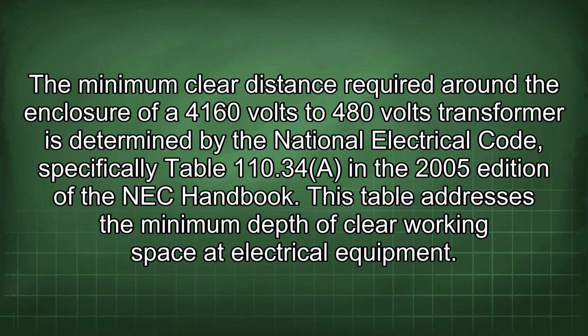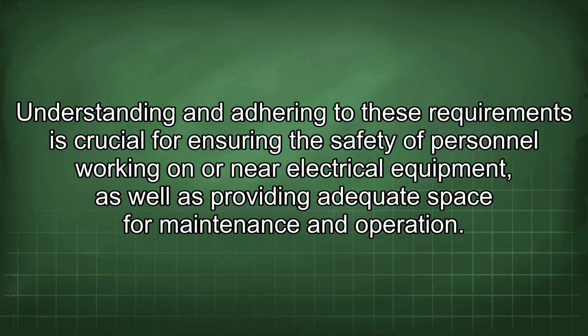The minimum clear distance required around the enclosure of a 4160 volts to 480 volts transformer is determined by the National Electrical Code, specifically Table 110.34 in the 2005 edition of the NEC Handbook. This table addresses the minimum depth of clear working space at electrical equipment. Understanding and adhering to these requirements is crucial for ensuring the safety of personnel working on or near electrical equipment, as well as providing adequate space for maintenance and operation.